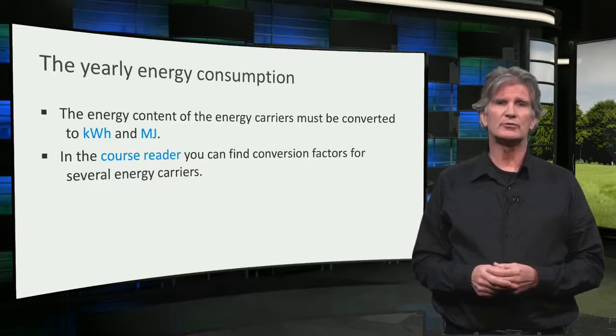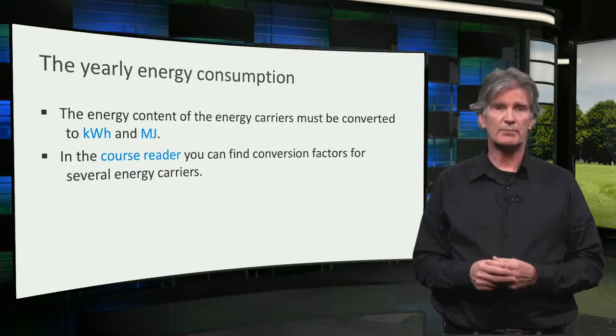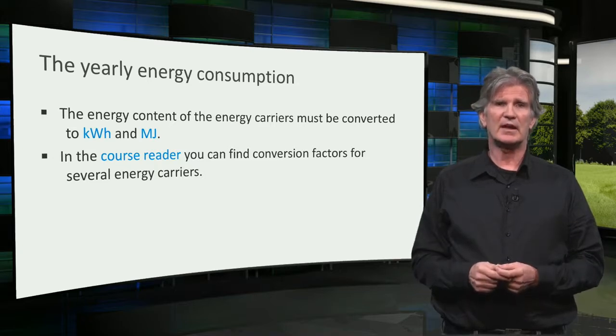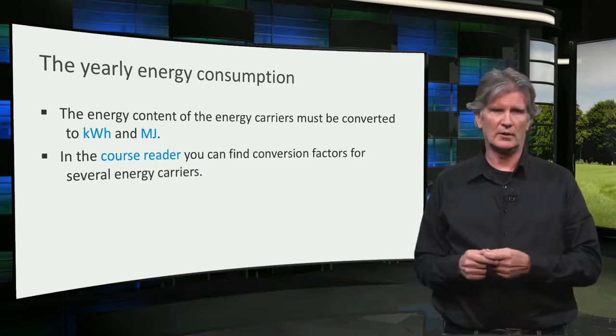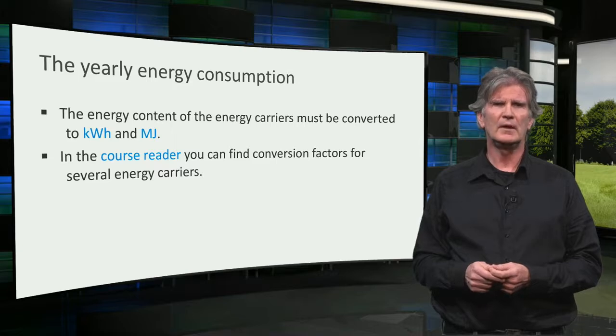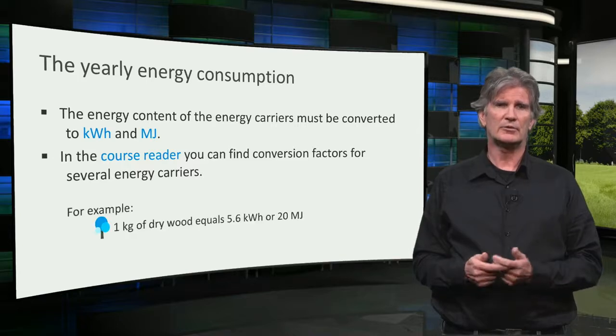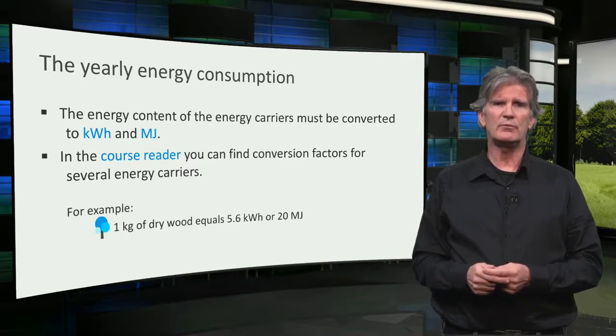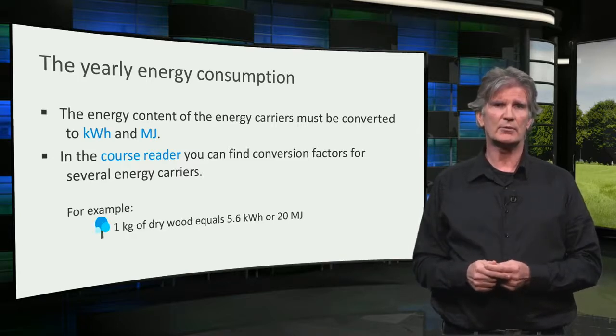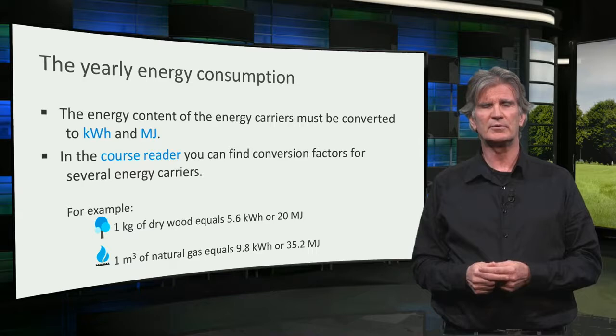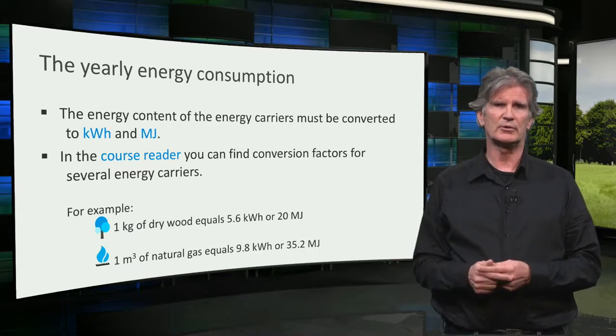When you have the data on the energy use of your building, it should be made comparable. Therefore, the energy content of the energy carriers must be converted to kilowatt hours and megajoules. In the course documents for this week, you can find conversion factors for several energy carriers. For example, one kilogram of dry wood equals 5.6 kWh or 20 megajoules, and one cubic meter of natural gas equals 9.8 kWh or 35.2 megajoules.